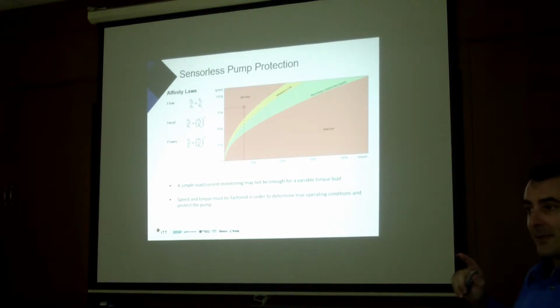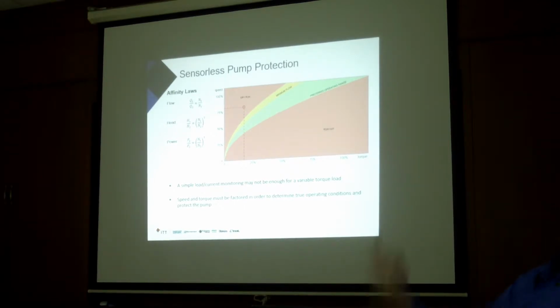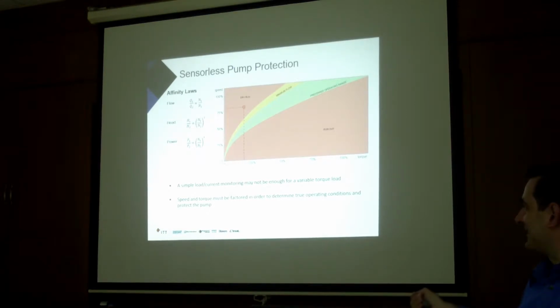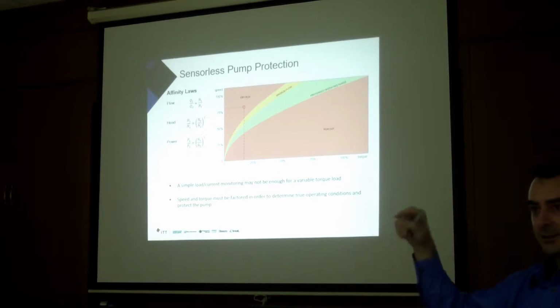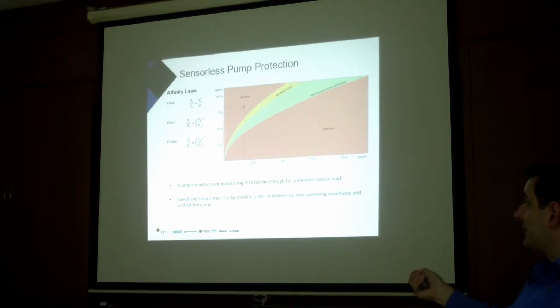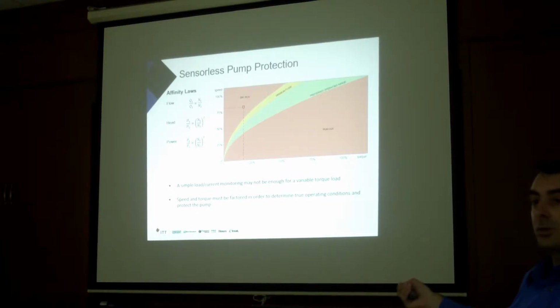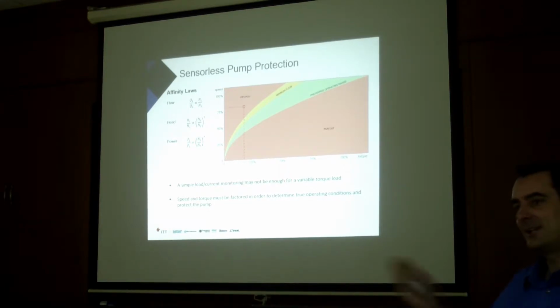So now they have it set for a full speed low enough. Now if you're running a pressure control system and you start dry running, what happens to the pressure? If you can't push any liquid in there, what do you think happens to the pressure? It goes down. So what's the first thing the pump's going to do? Speed up. So you can see where I'm going. If you have a pressure control system and you start dry running, you are going to hit maximum speed, 100%, because the control logic will say, I've not got enough pressure, increase my speed. So you will operate here. So many times we can show a customer that using just torque is not going to help, because as soon as they lower, they trip again because they're below 50% torque. So they need to compromise.